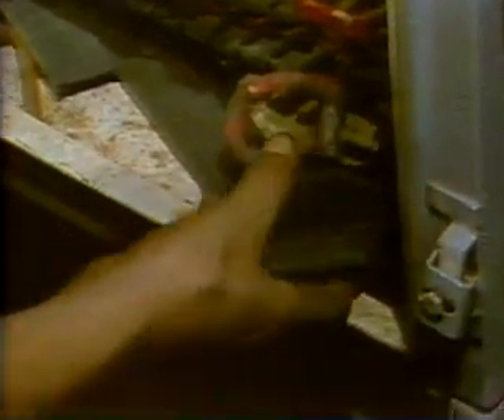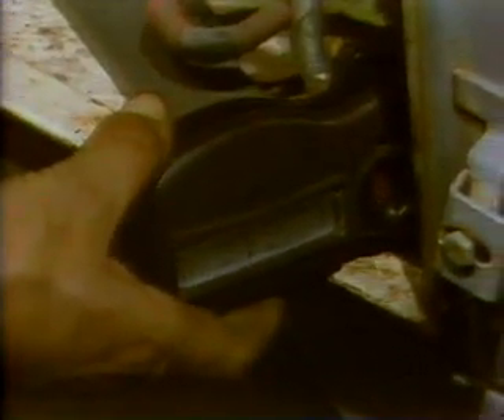High amperage readings at the compressor motor indicate a possible low voltage or unbalanced leg in the three-phase power to the compressor motor, which may cause overheating and possible motor failure. If you notice that high readings have been logged into that space, bring this to the attention of the electrician so that he can troubleshoot the problem.